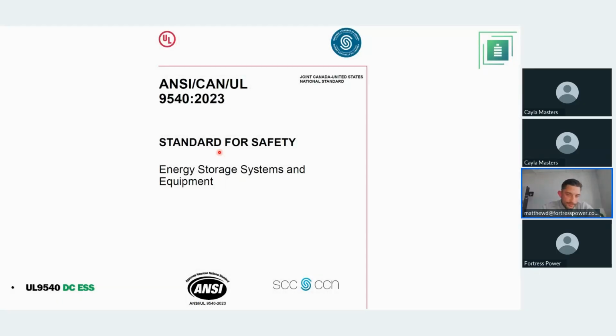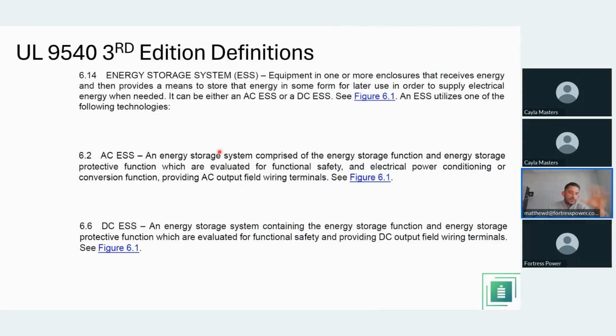So I will now talk about the UL 9540 DC ESS, right? To give a little bit of context, UL used to certify batteries in this manner: it had to be UL 9540 on the first edition, and it would just certify the battery. On the second edition, UL 9540 required you to certify the battery together with an inverter, right? So both solutions had to be implemented and certified under that standard. On the third edition, they changed the definitions a little and included both solutions, right?